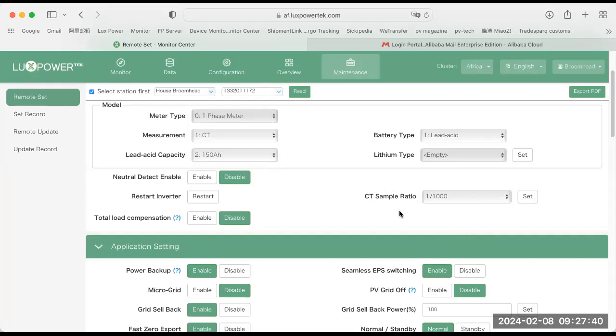Here on the CT sample ratio, you have 1 in 1,000 and 1 in 3,000. It's shipped standard with 1 in 1,000 as a default, and that is because the CT clamp that we use, which is supplied by an external supplier, is a 1 in 1,000 sample ratio. So please do not change this unless, of course, you are changing your CT. And the only time you will change your CT clamp is if you are installing your CT at a much further distance away from the machine, longer than what the cable is.